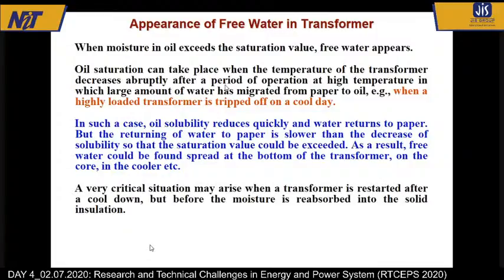Then when the transformer is started again, you know the cooling fans start fast. What will happen? They will draw the oil from the bottom of the tank and then send it through the cooling tubes back to the top of the tank. So when the transformer starts again, these cooling fans draw the oil from the tank and it will almost like a spray come from the top of the tank onto the transformer winding. This has happened many times. So people take adequate care nowadays.